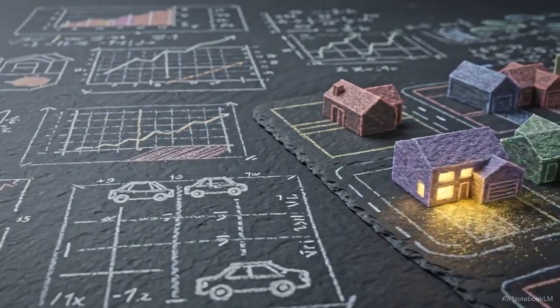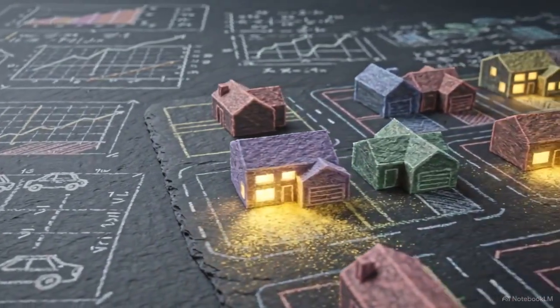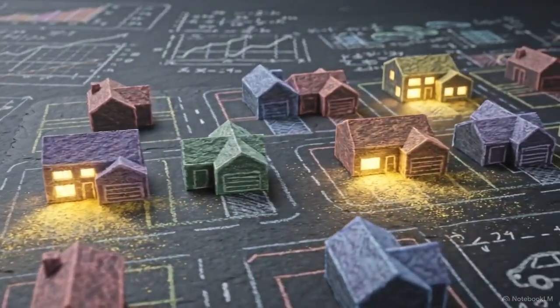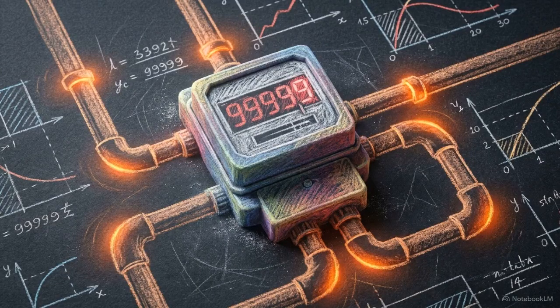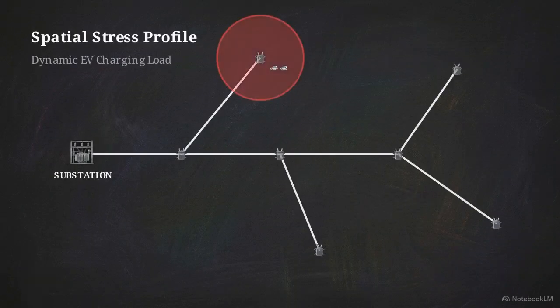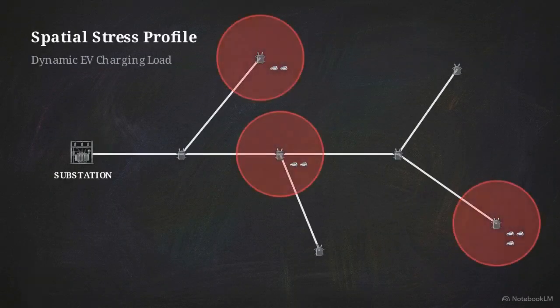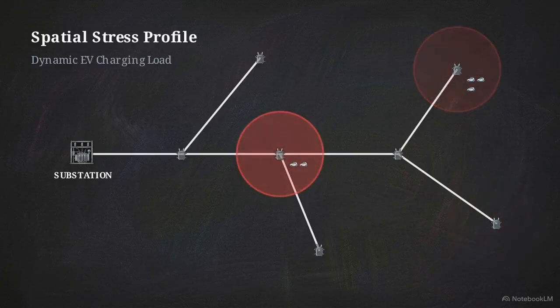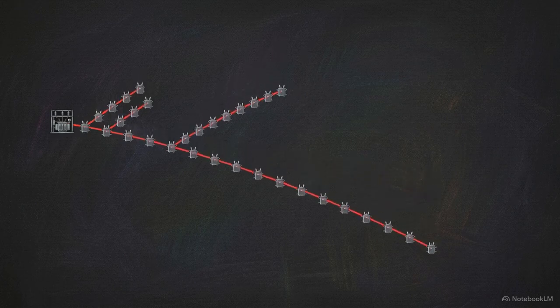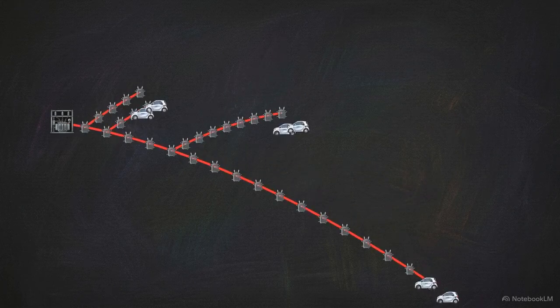As dusk settles over a dense suburban neighborhood, residents return home and immediately plug in their electric vehicles. This nightly routine creates clustered charging events, triggering localized power surges across residential grids. These simultaneous charging events shift the physical location of the electrical burden, changing the spatial stress profile of the distribution feeder minute by minute. The physical consequences of this sudden reactive power demand are measurable. Branch currents experience severe nonlinear spikes, which in turn force the nodes further downstream into sharp voltage sags.